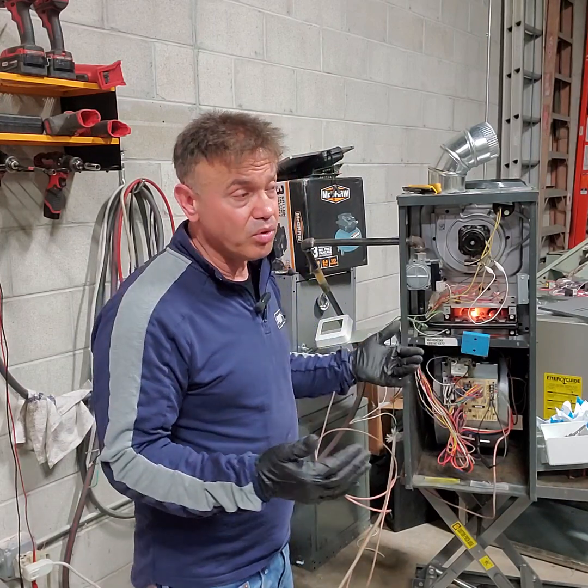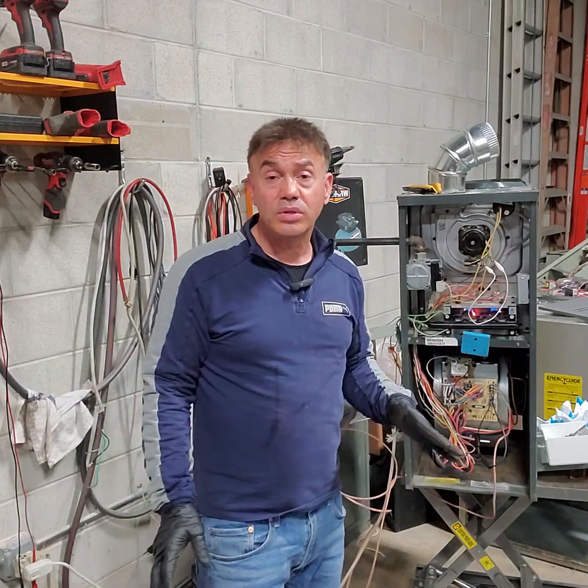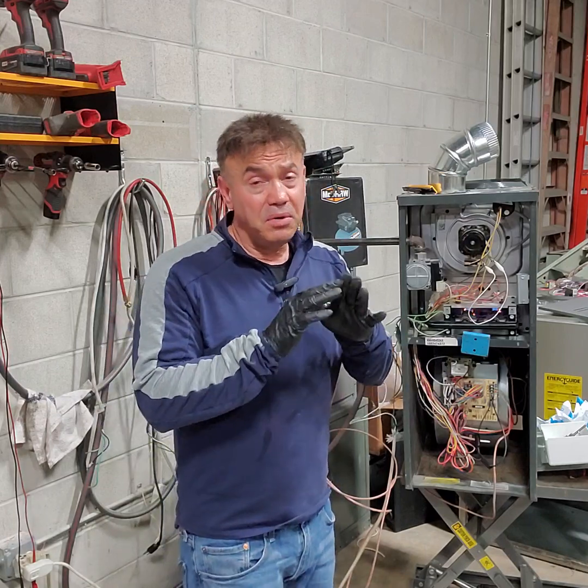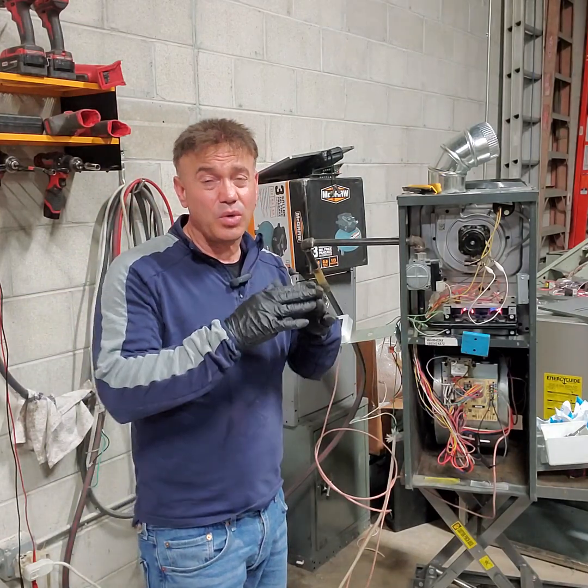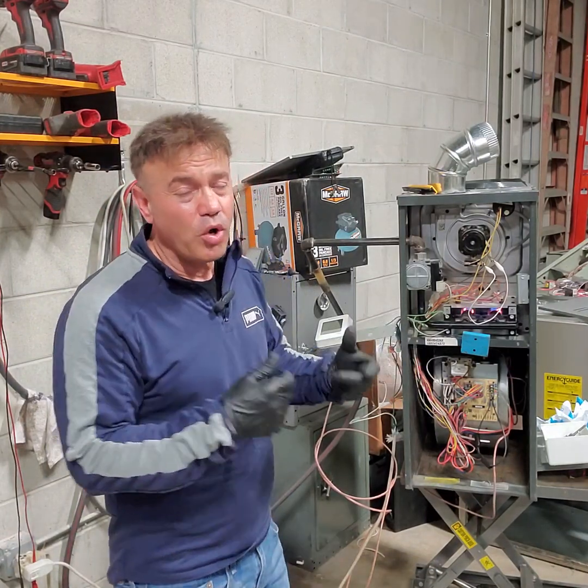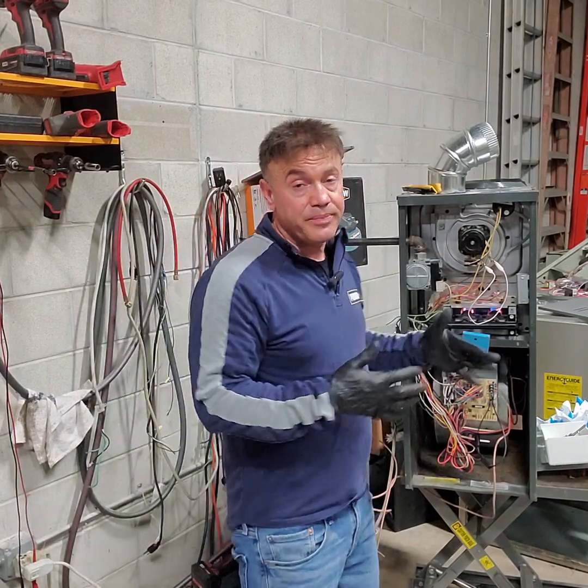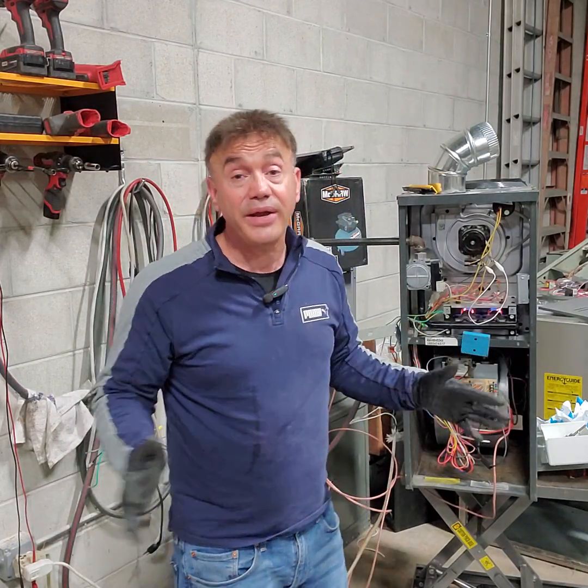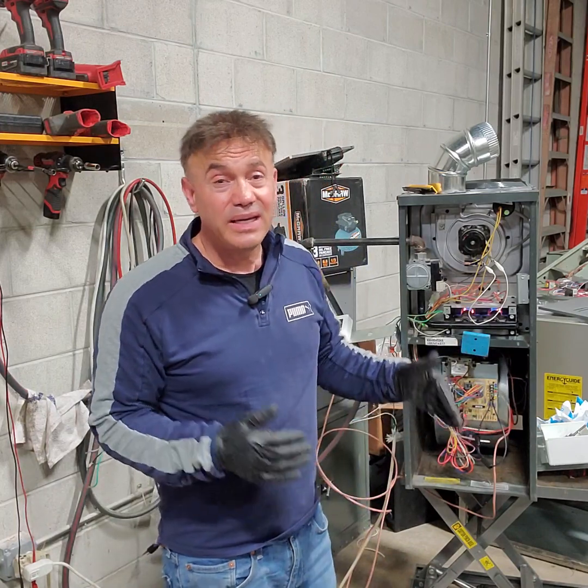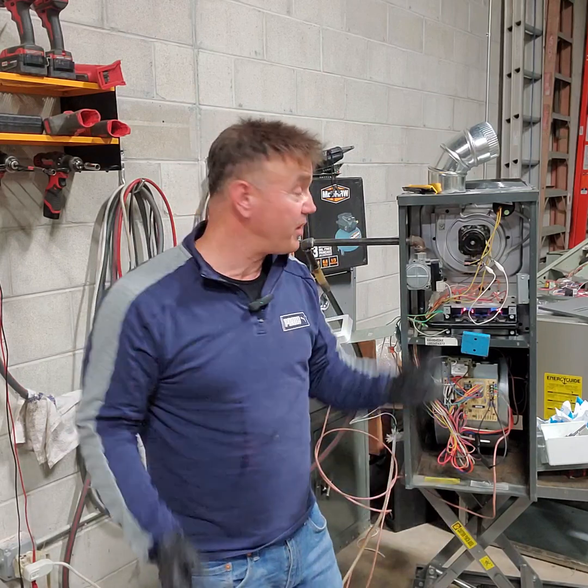I tell the homeowner, hey, it's gonna run only one time. It's 12 o'clock now, and it's 0. So the only thing you can do, turn the thermostat to 80. It's okay. It's always better to be frying than it goes to 40 or 50. And I will tell him, as soon as it goes to 80, sometimes some homeowner can be very handy. I tell them, hey, when you turn it on, jump that and remove it. They can do it. Sometimes they don't know how to do it. So I just tell them, put it at 80 or 85. I don't care. Fry. So when the thing stops, it takes forever to go back to 60. So by the time it's morning, I go to grab a new one, you're going to be fine.